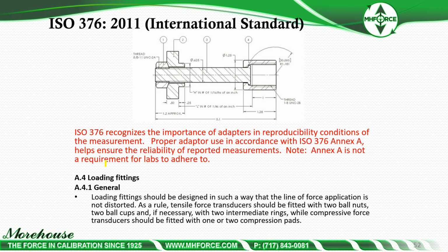And in general, Annex A 4.1 says load fittings should be designed in such a way that the line of force application is not distorted. Again, keeping that line of force pure from eccentric loads. As a rule, tensile force transducers should be fitted with 2 ball nuts, 2 ball cups, and if necessary, with 2 intermediate rings, while compressive force transducers should be fitted with 1 or 2 compression pads.